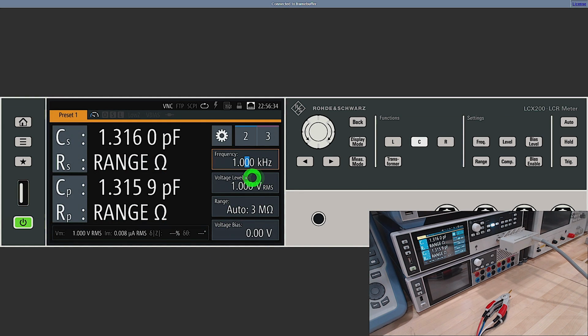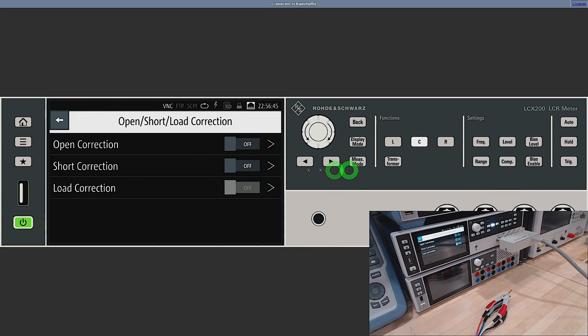Now the voltage level applied here is 1 volt RMS. I'm going to set the range to auto. I'll talk about the auto ranging a little bit later on. But let's get rid of this coupling capacitor here. So if you go under compensation, under compensation you have open and short correction as well as load correction, which is very typical for LCR meters.